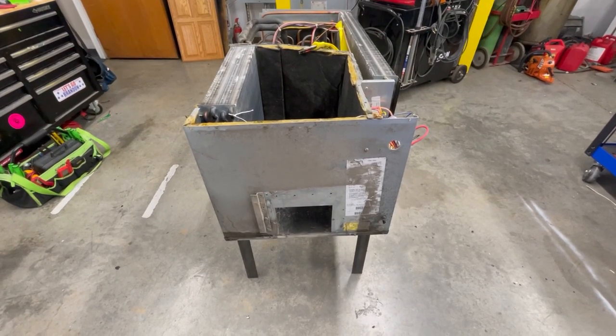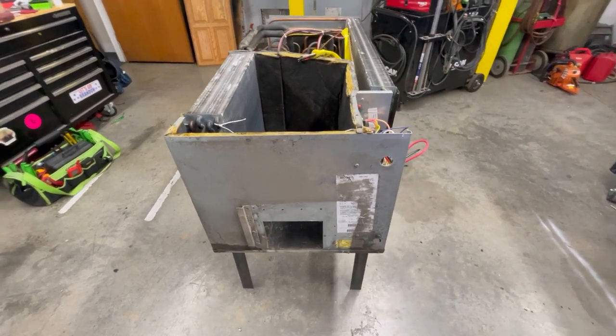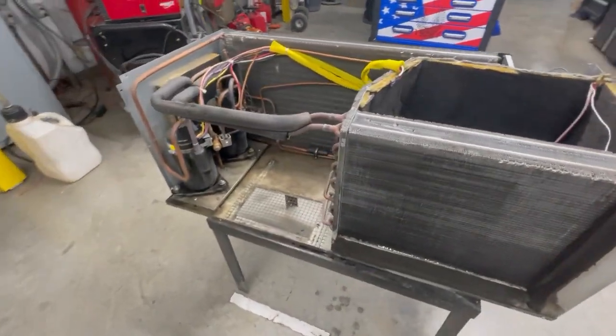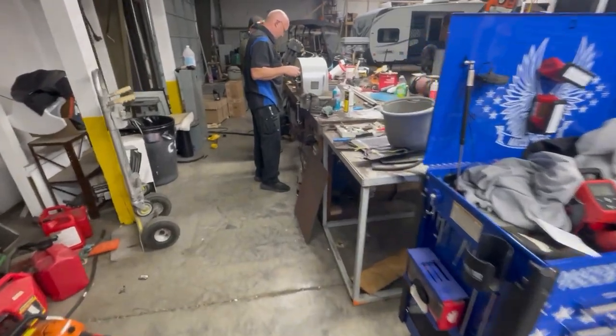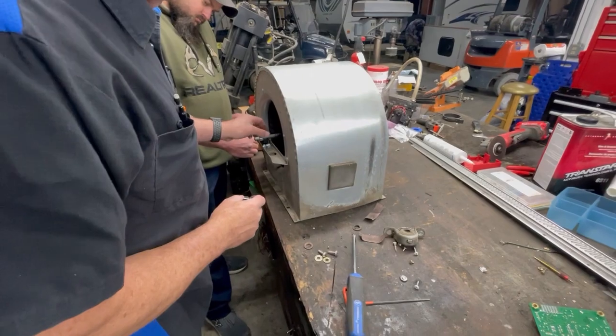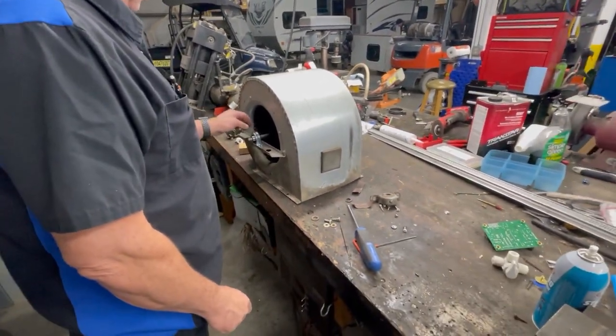Welcome back. So this basement air out of this Winnebago Journey is actually a 16 model. 46515-811, built in 16. And remember last week when we looked at that, it was just filthy nasty. Lewis and Cody have everything washed out real good, and they are working at the moment at changing out the bearing on the outdoor fan, which we always change because we always have trouble out of those going from that style to that style. So once we get that changed out, they're going to put that back in and retest.